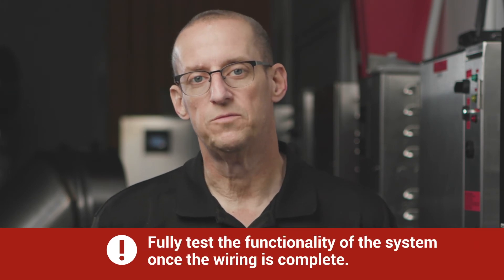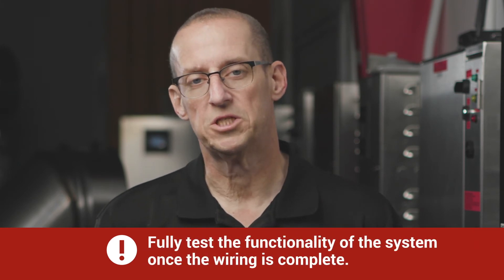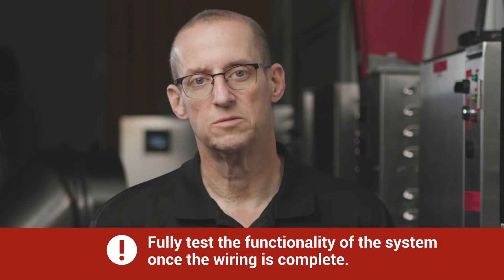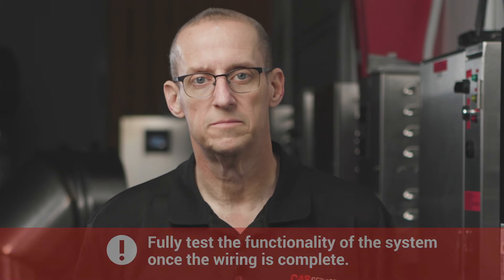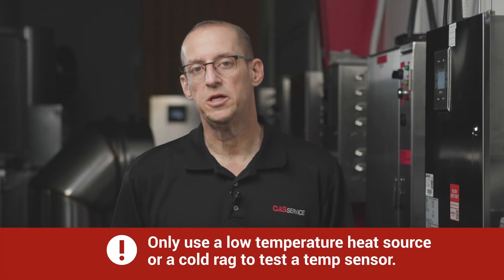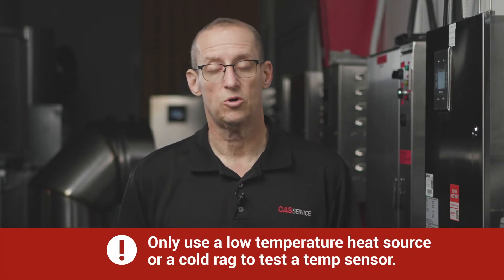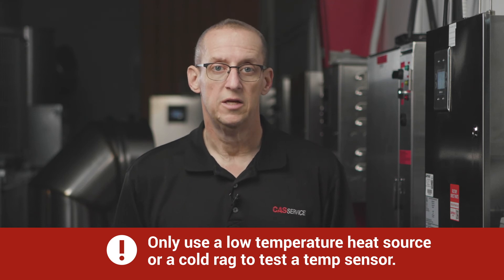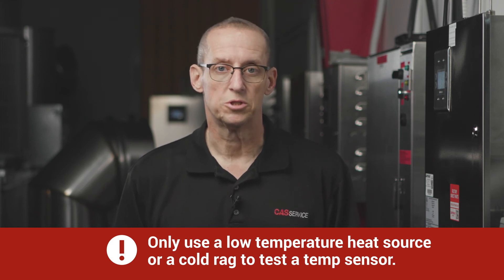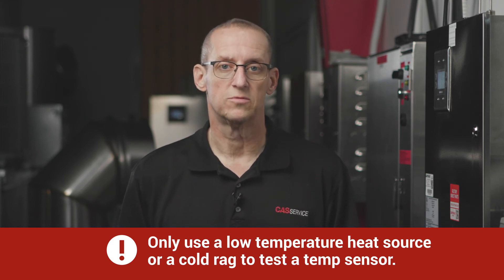As always, once the temp sensor wiring is complete, it's recommended that you fully test the functionality of the system to ensure everything's running correctly. Just a reminder, only use a low temperature heat source or a cold rag to test the temp sensors. Never use a torch or heat a temp sensor for a long period of time.